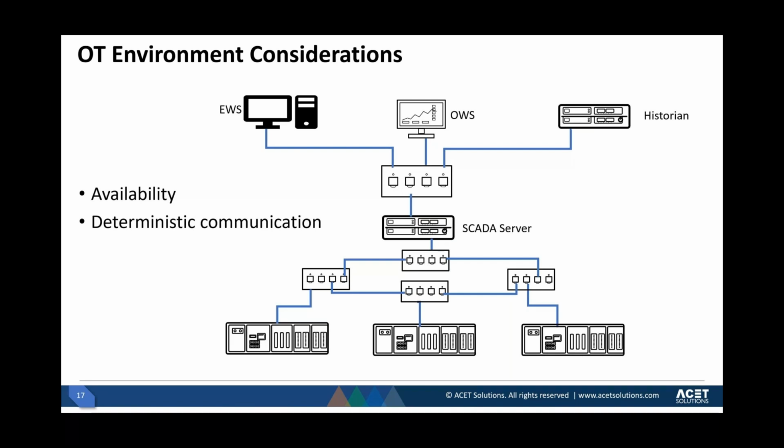I've seen literally within the past year in some of the high-end refineries, at the lowest level of PLC communication, some kind of Ethernet ring, where the switches are connected in a ring topology using Rapid Spanning Tree Protocol, RSTP. Another problem with this protocol, if not properly configured, is that it is very sensitive.